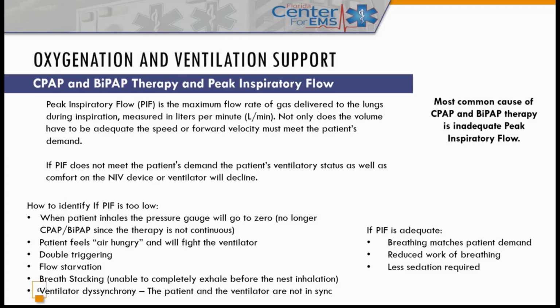If the peak inspiratory flow is adequate, the breathing matches demand, reducing the work of breathing and the need for sedation. I've seen people want to sedate a patient because they were fighting the machine, but if you look at their numbers, you realize the machine is creating the problem. They might have their hands tied down, fighting everything, because we're not providing proper ventilation with the settings we're using. So that's something you have to continue to monitor to make sure they're not having an issue.